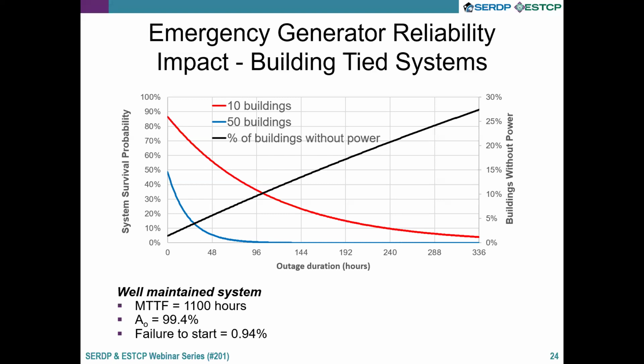You need to remember, though, you can't know ahead of time which buildings will be failing. This is a fundamental problem with emergency generators. Historically they were used for very short duration. They're designed, and well designed, to support backup power for 4, 8, or 12 hours. They were never intended to be used individually as standalone assets for multiple days to multiple weeks, and so they cannot provide the type of reliability and energy resilience that DoD requires.